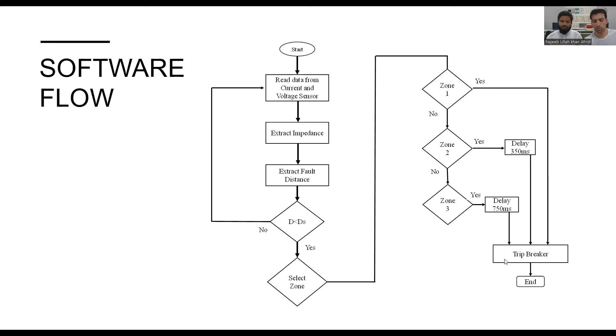If it lies in the first zone, it will generate a trip signal instantaneously. If it doesn't lie in the first zone, then it checks whether it lies in zone 2. If it lies in zone 2, then it takes a delay of 350 milliseconds and then generates a trip signal. If it doesn't lie in zone 2, then it checks if it lies in zone 3. If it lies in zone 3, then the relay takes a 750 millisecond delay, and then the relay generates a trip signal, and then our program ends.